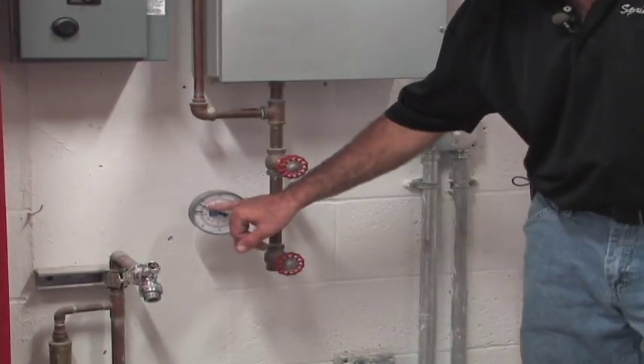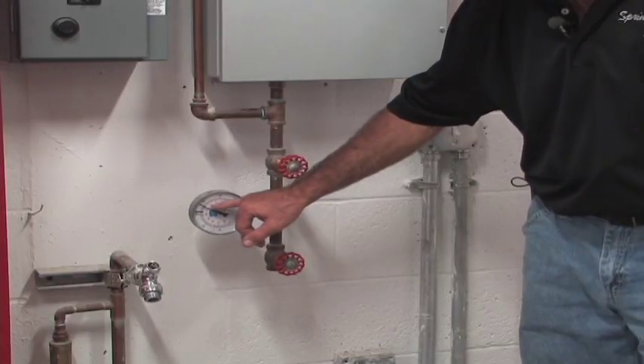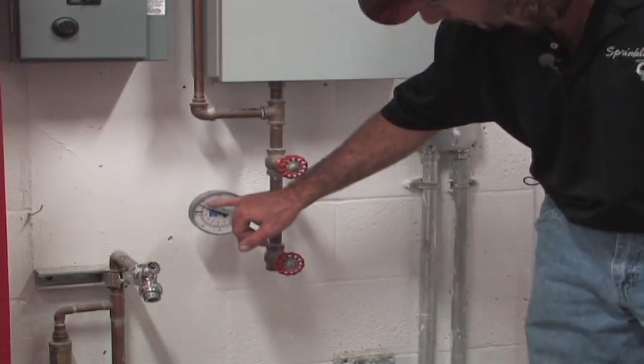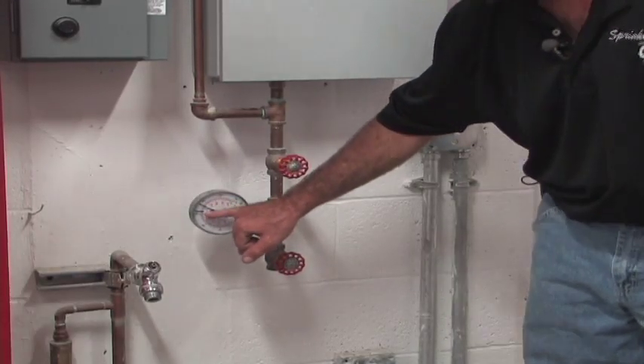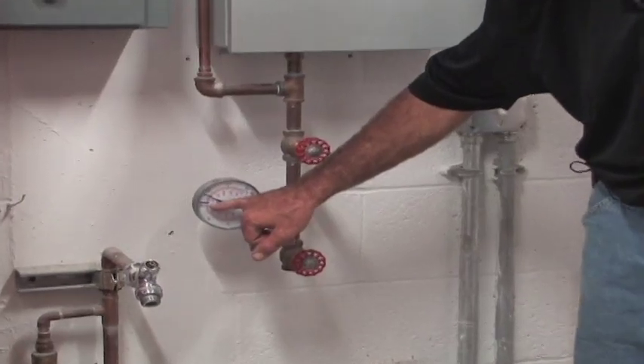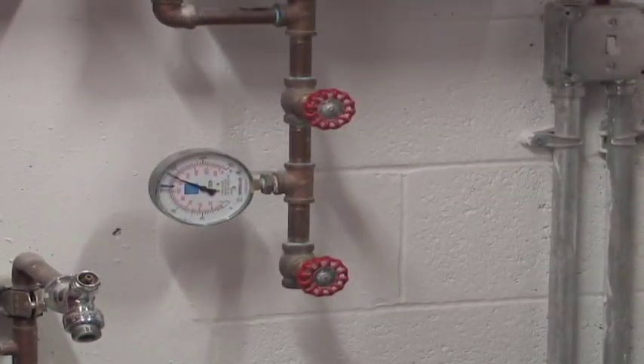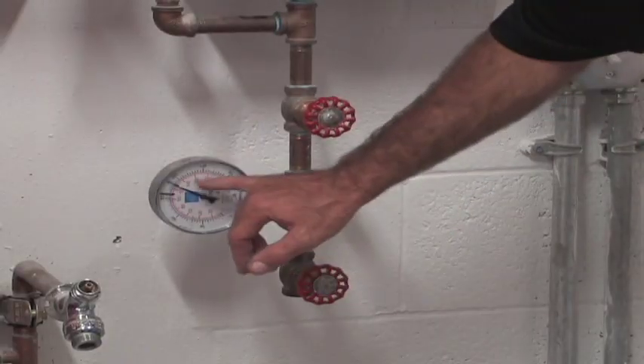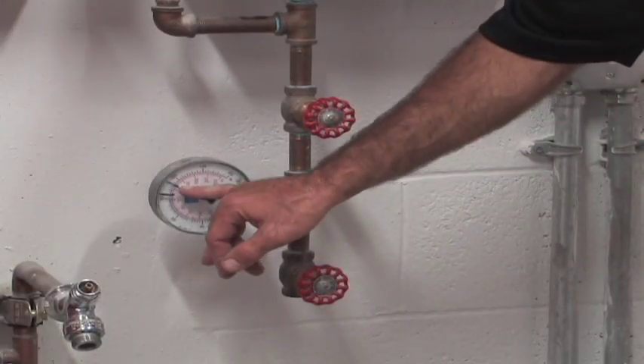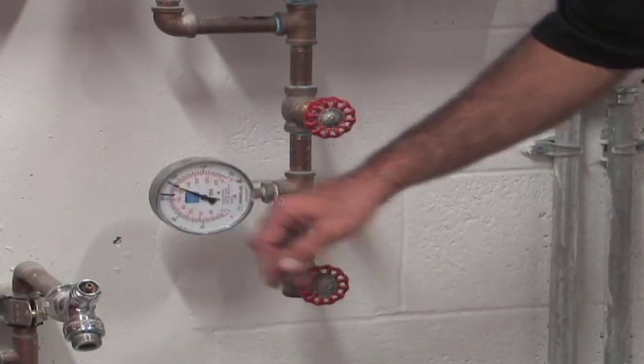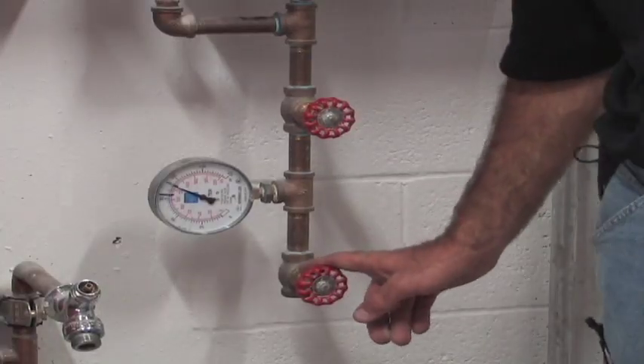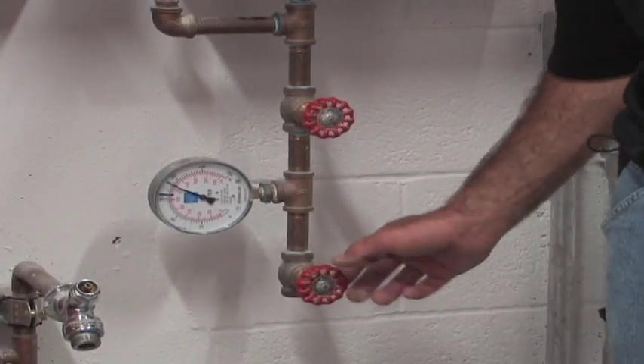As this goes over on a daily, weekly basis, as we lose pressure in the sprinkler system, when we get down here to our black mark, which is going to be our start at 160 psi, the jockey pump's going to cycle on and it's going to shut off at 180 automatically. We're going to run through that procedure, and then, like I said, it would be just our jockey pump.